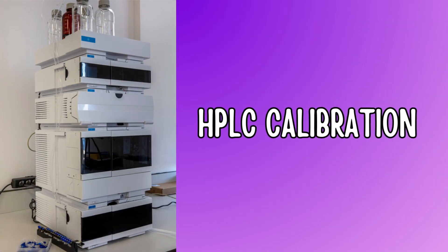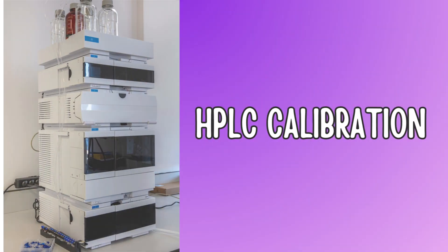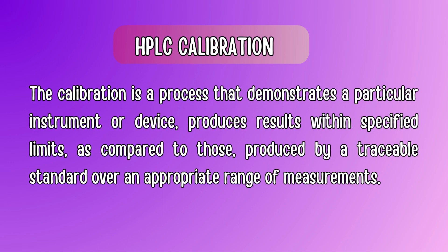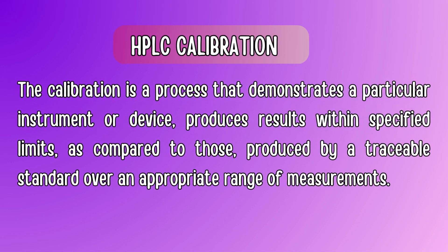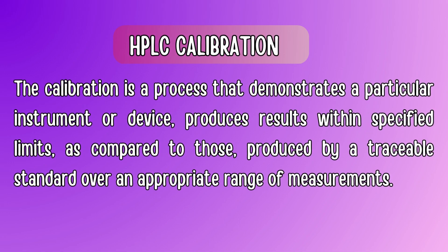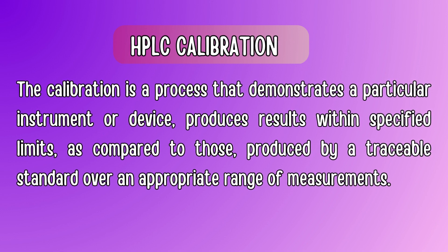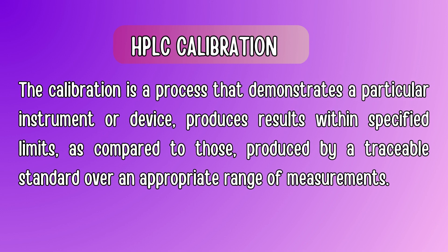In today's video, we will discuss HPLC calibration. First, we will understand what calibration is. Calibration is a process that demonstrates a particular instrument or device produces results within specified limits as compared to those produced by a traceable standard over an appropriate range of measurements.